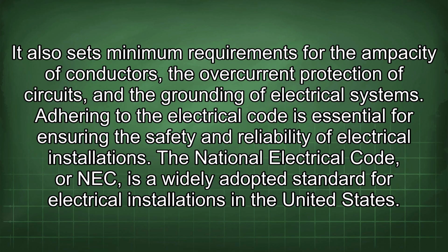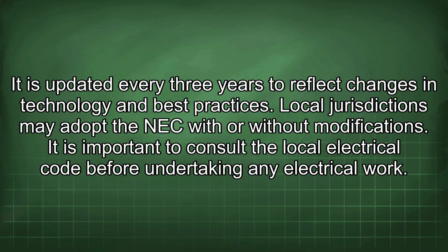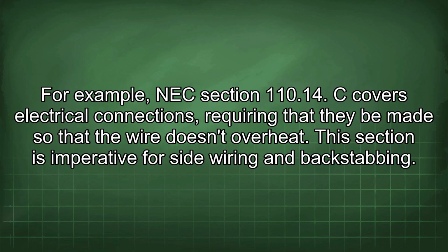The National Electrical Code, or NEC, is a widely adopted standard for electrical installations in the United States. It is updated every 3 years to reflect changes in technology and best practices. Local jurisdictions may adopt the NEC with or without modifications. It is important to consult the local electrical code before undertaking any electrical work. For example, NEC Section 110.14(C) covers electrical connections, requiring that they be made so that the wire doesn't overheat. This section is imperative for side wiring and backstabbing.